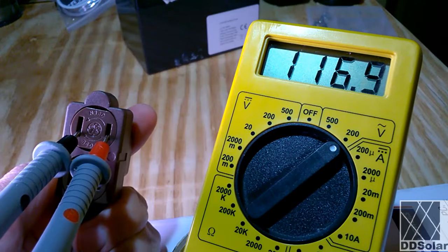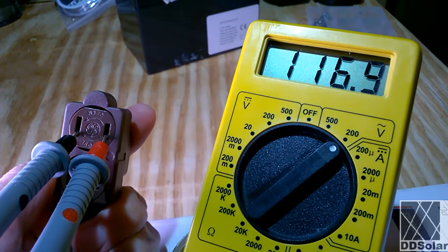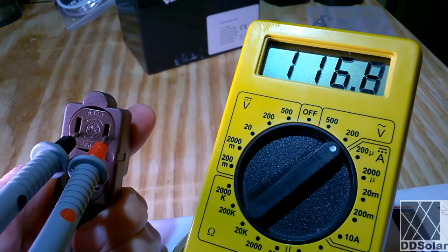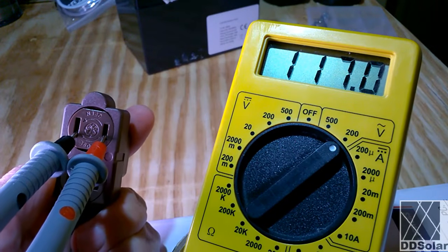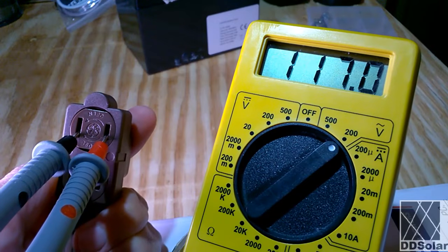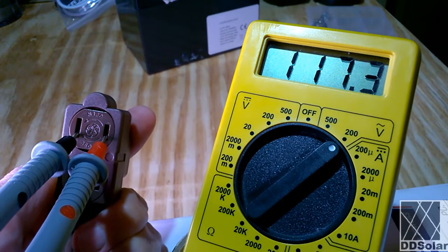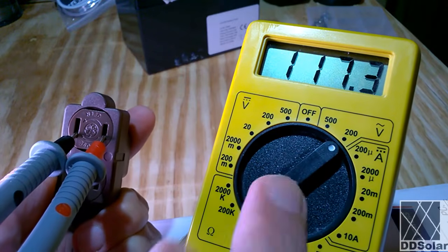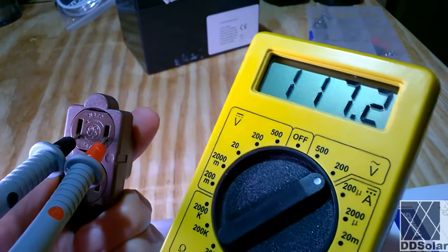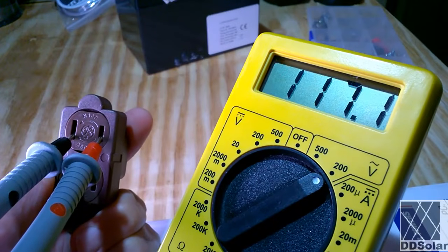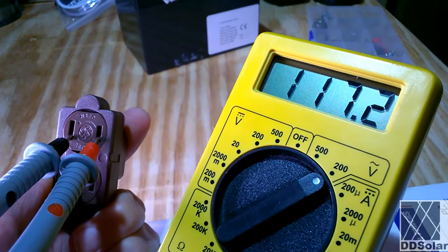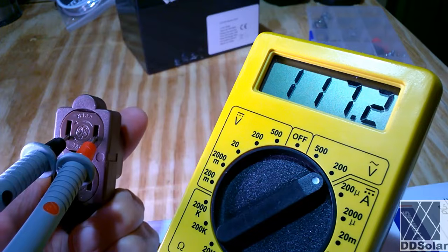If it drops to almost nothing or under 100 volts, you know there's something wrong. It could be a bad extension cord, a bad appliance, and it could mean that there is a bad connection somewhere. In this case, the cord has no load on it, and so I'm not going to see a voltage drop. There is some variation, and that variation is happening on the meter because this is a live household with appliances being turned on and off. Things are changing, things are powering on and off, and so there is going to be some variation in the line voltage, and having a single decimal place is enough to see even small changes. It's very interesting to watch.